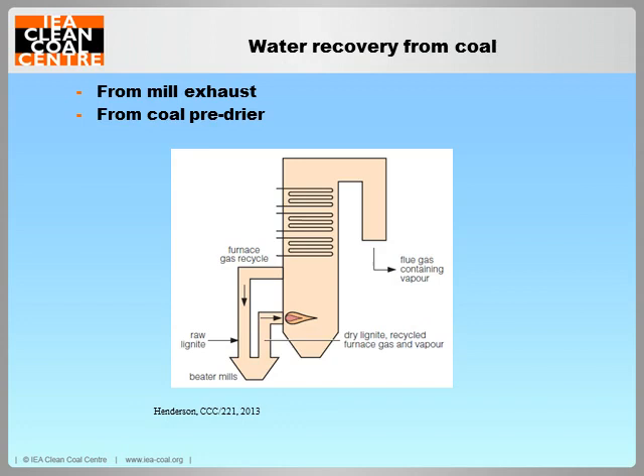But using high-grade heat to dry the coal and passing all the evaporated moisture through the boiler results in lower power efficiencies and higher CO2 emissions than from plants firing coals with a lower moisture content at similar steam conditions. So instead, the coal could be dried, preferably using low-grade heat, and the evaporated moisture captured from the mill exhaust. Or the coal could be pre-dried and the moisture captured before the coal enters the mill.